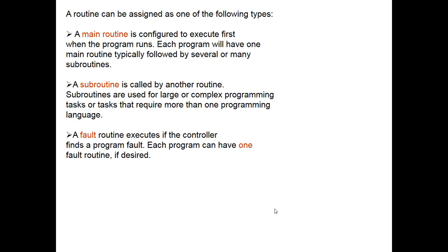The routine has to be programmed in the same language, but you can choose from a variety of languages: ladder logic, function block, structured text, or sequential function chart. The entire routine has to be in one language. So you can have the first routine programmed in SFC, the second in ladder, and the third in function block — you just can't have both in the same routine. Then they get scheduled. We'll have a main routine that executes continuously, subroutines or function blocks that need to be scheduled out of the main routine, and fault routines that interrupt other routines when a fault is found.